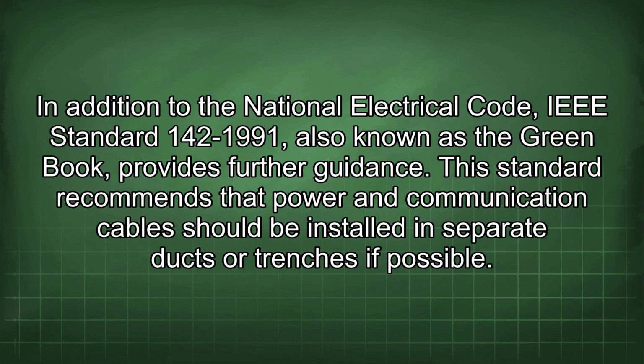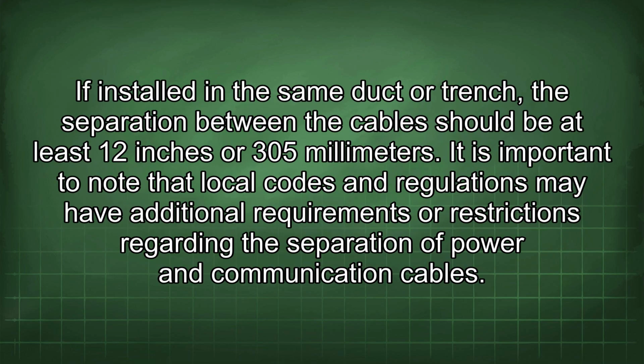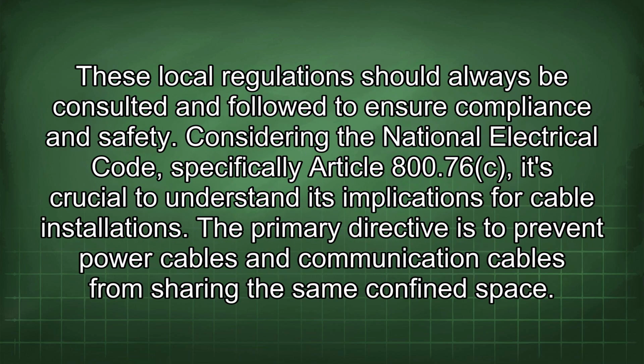In addition to the National Electrical Code, IEEE Standard 142-1991, also known as the Green Book, provides further guidance. This standard recommends that power and communication cables should be installed in separate ducts or trenches if possible. If installed in the same duct or trench, the separation between the cables should be at least 12 inches or 305 millimeters. It is important to note that local codes and regulations may have additional requirements or restrictions regarding the separation of power and communication cables. These local regulations should always be consulted and followed to ensure compliance and safety.